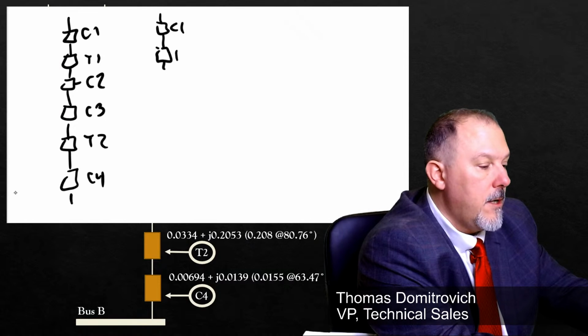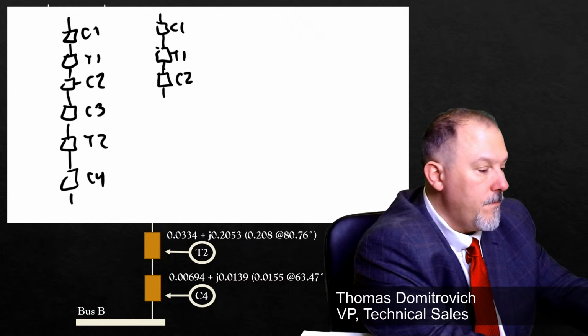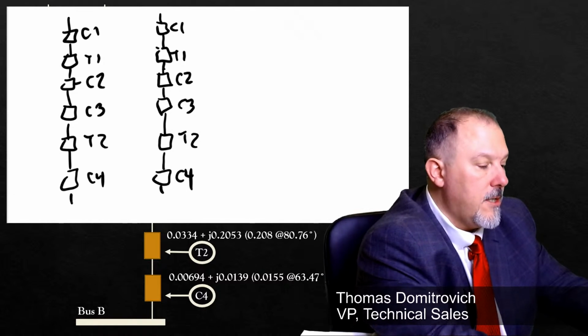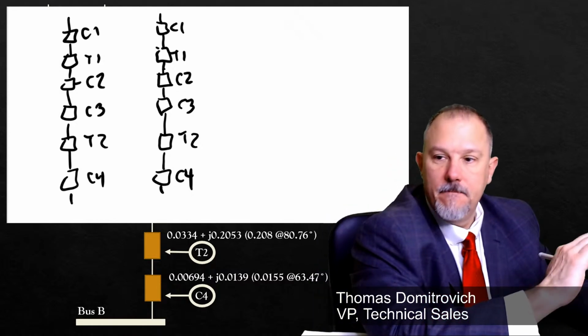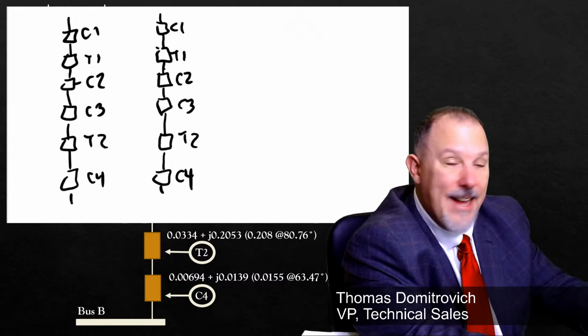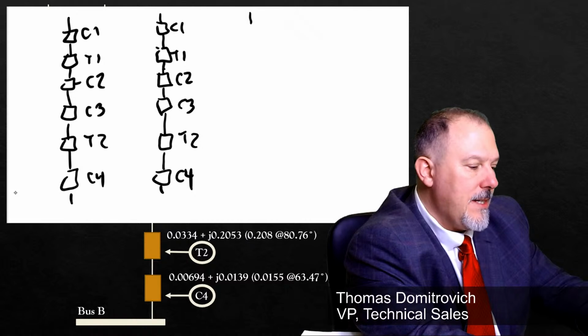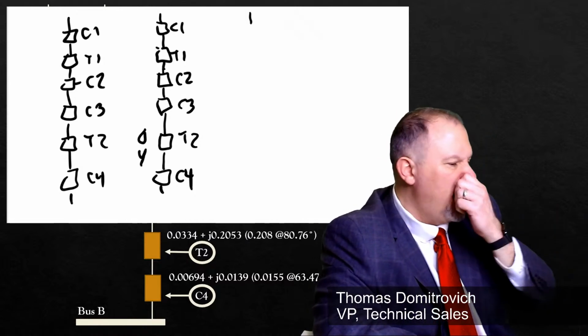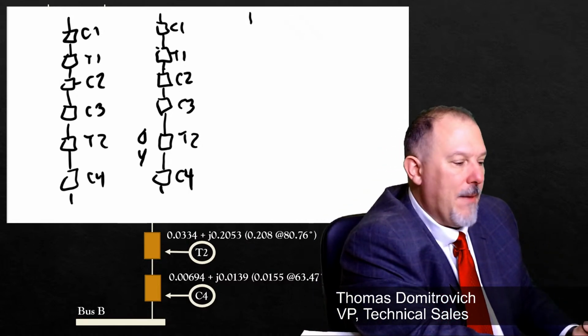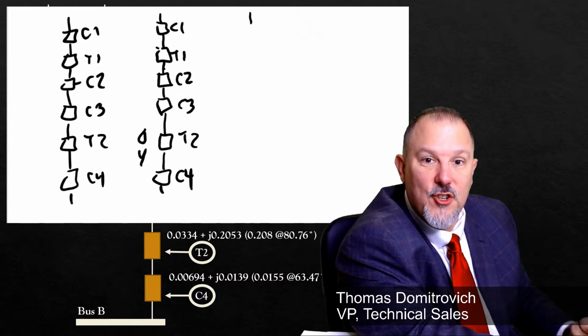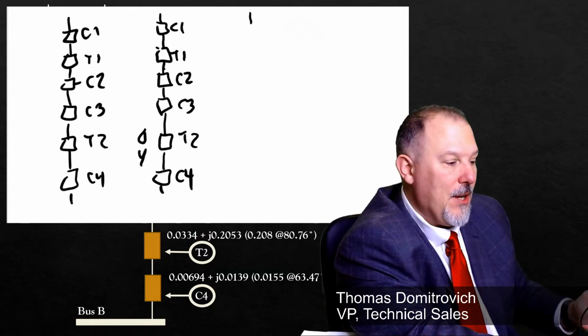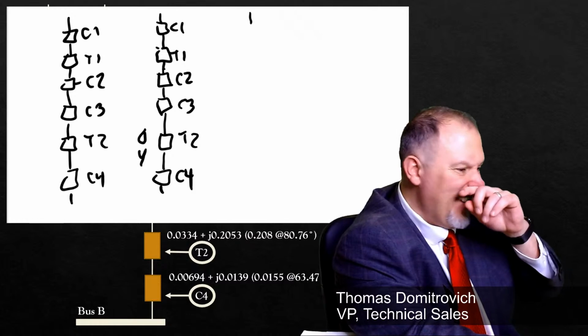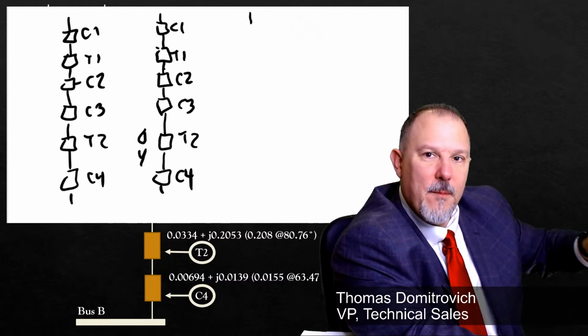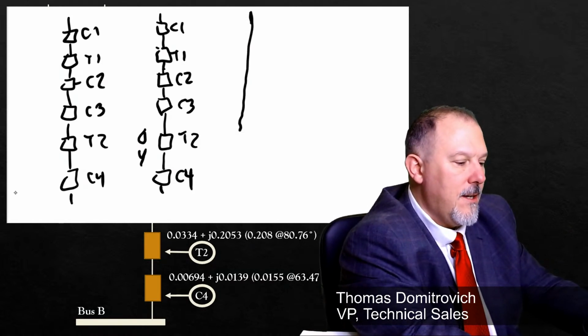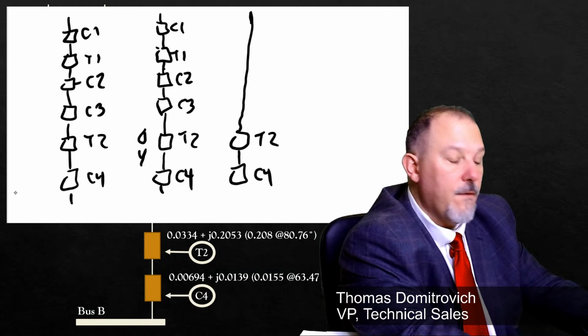What's my negative sequence? Conductor 1, transformer 1, conductor 2, conductor 3, transformer 2, conductor 4. Exactly the same as my positive sequence. Thanks, Felix. Now, my zero sequence. Remember, this is a delta Y ground transformer, transformer 2. Don't make the mistake of thinking that for my ground fault I have to include conductor 3, transformer 1, and conductor 2 because that's a delta Y ground, a Y grounded on the secondary of that upstream transformer. I'm isolated from that. For my zero sequence, everything is short circuited down to T2 and conductor 4.